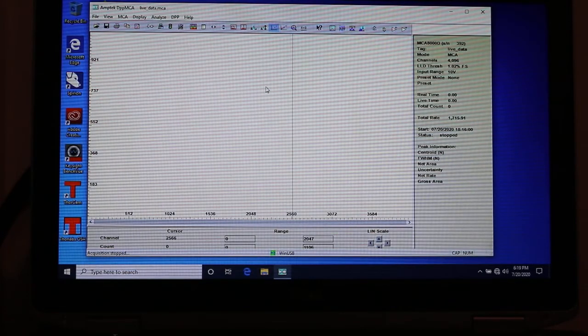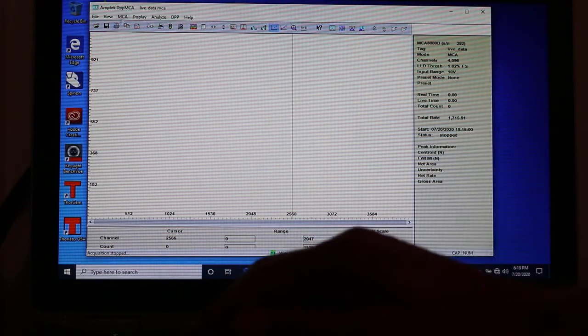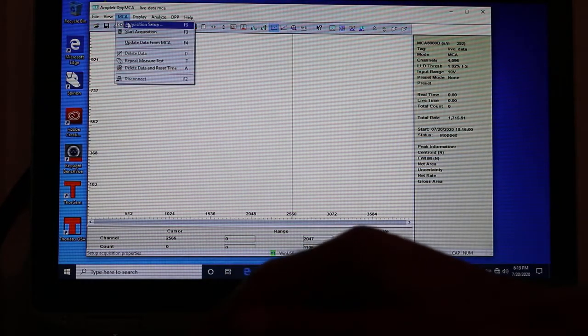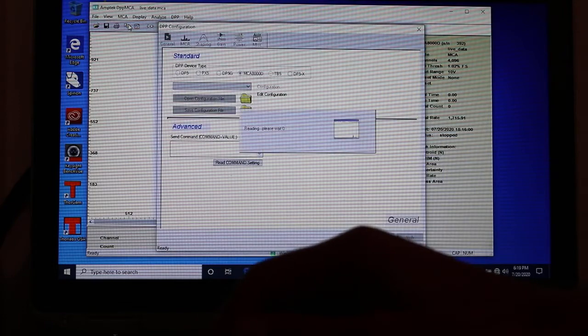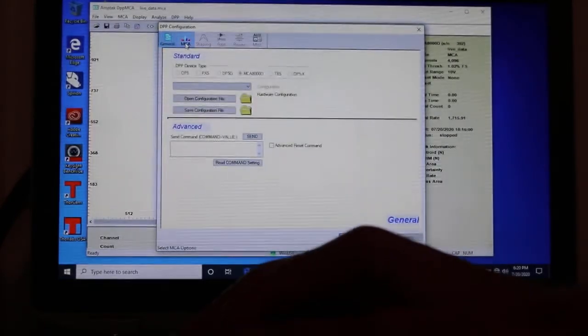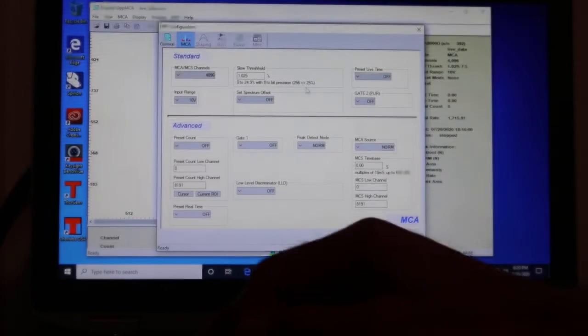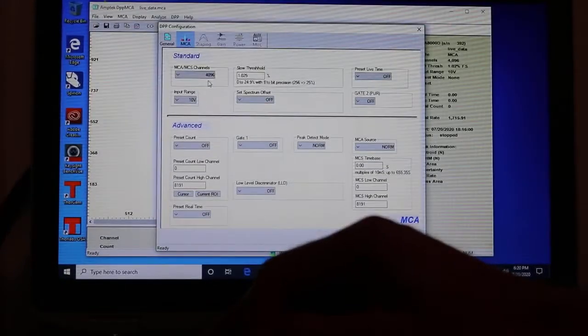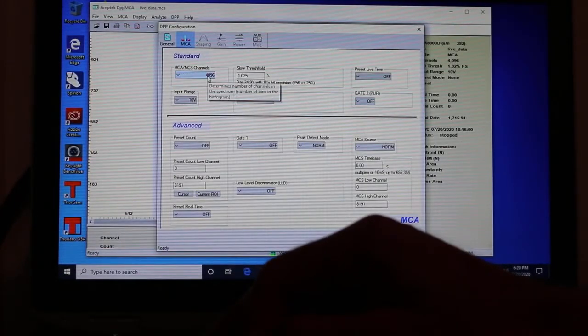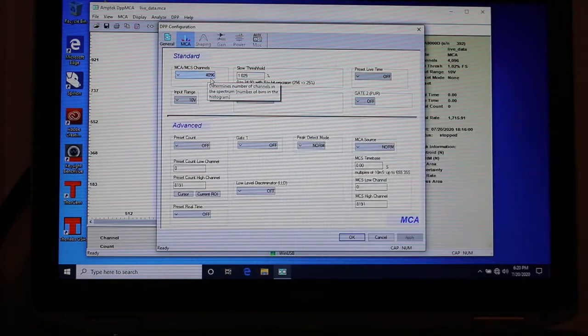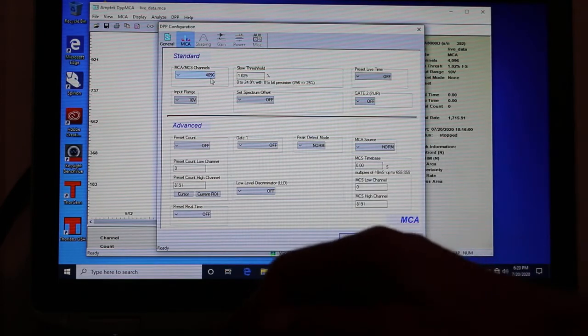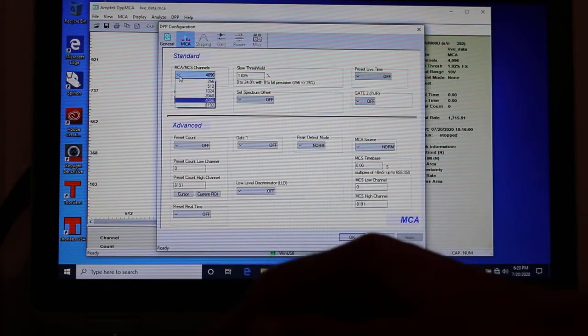So what exactly does this software do? Let me go up to the settings here and show you what one of the configuration menus looks like. We go up to MCA and do acquisition setup. So the first thing it allows me to do is I can change the number of channels that we have. 4096, that would be the extreme x-axis location at the moment. So at the moment the channels run from 0 to 4096, which is a power of 2.